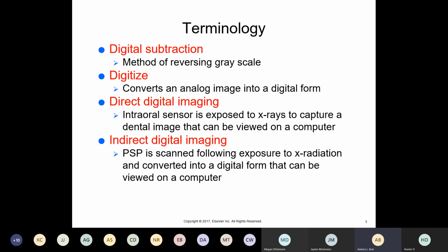The PSP plates can also be damaged by a patient biting on them because they're very much like film. They're reusable. We have to erase them. I think a lot of the scanners now will scan and erase all in one step, but we used to have to scan ours in, wait for them to be scanned and drop out of the scanning machine, and then we would lay them on what looked like a little tanning bed, it was a light, and you'd close the lid and set it for a certain amount of time so that it would erase the image that had been captured on those phosphor crystals, and then we would put them in a new sleeve.